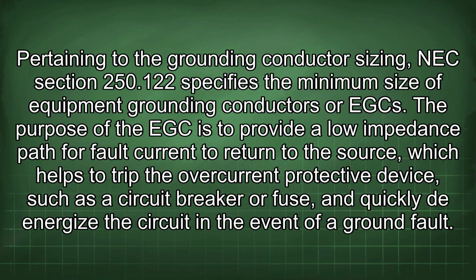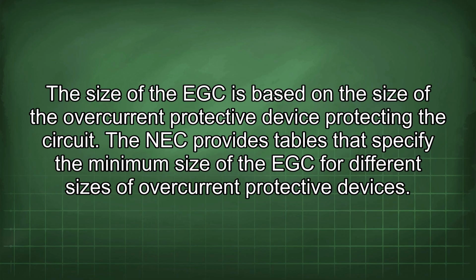Pertaining to the grounding conductor sizing, NEC section 250.122 specifies the minimum size of equipment grounding conductors or EGC. The purpose of the EGC is to provide a low impedance path for fault current to return to the source, which helps to trip the overcurrent protective device, such as a circuit breaker or fuse, quickly and de-energize the circuit in the event of a ground fault. The size of the EGC is based on the size of the overcurrent protective device protecting the circuit.